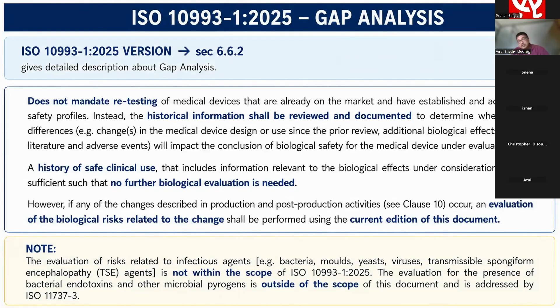The limitation of the standard is the evaluation. It is written in the note that the evaluation of the risk related to infectious agents like bacteria, mold, yeast, virus, and TSE agents is not within this standard. So when you are talking about microbiological concerns of your device and animal agents, it is beyond the scope of these biological evaluations. It also does not talk about the bacteriological evaluation, that is, bacterial endotoxin that is present on your device. So this is the main limitation of this latest version.